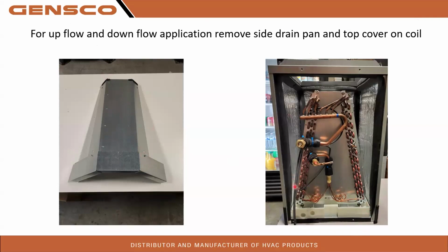The horizontal drain pan comes out along with the brackets. Very important you do this for your upflow and downflow application. That way you get proper airflow across that coil. If you don't have it there, then you're impeding airflow by quite a bit. You want to make sure we get that removed.